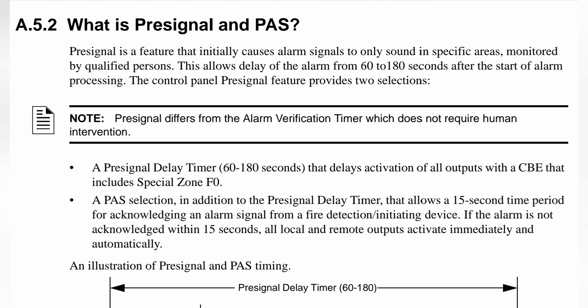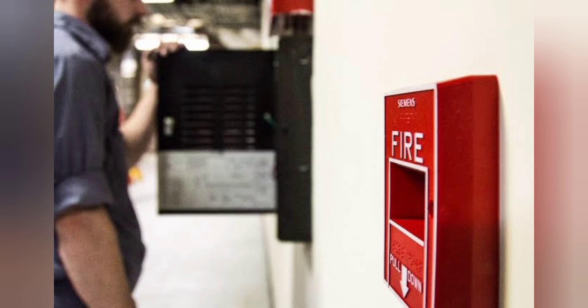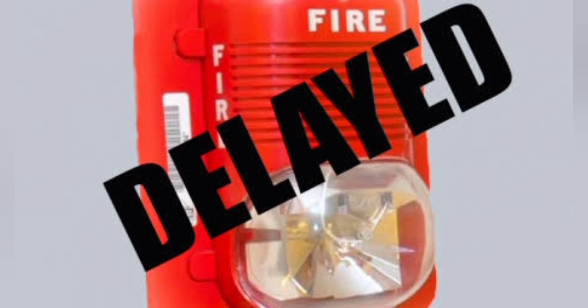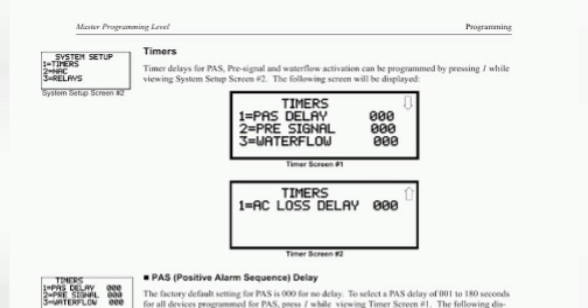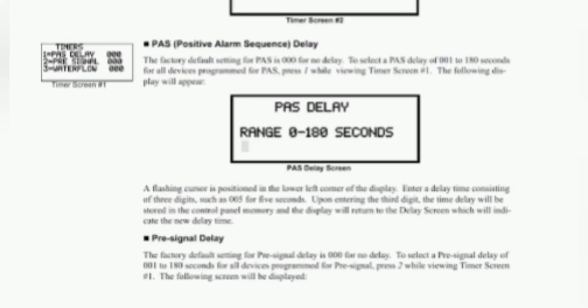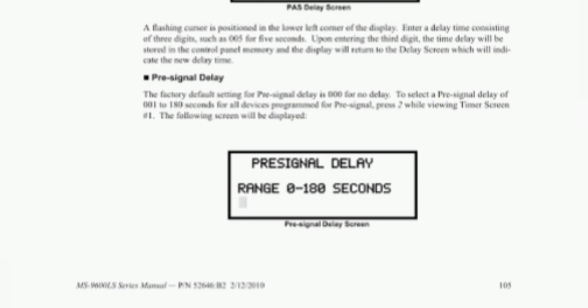Positive alarm sequence is an automatic visual or audible pre-signal that occurs in an area of the facility that is constantly monitored, which creates a short delay between the time it sounds and when the general alarm initiates throughout the building and alerts emergency personnel.